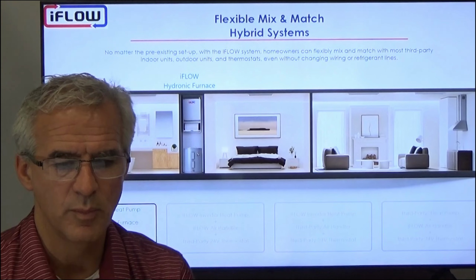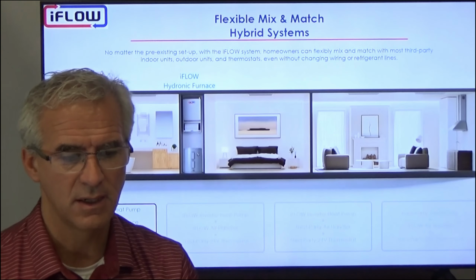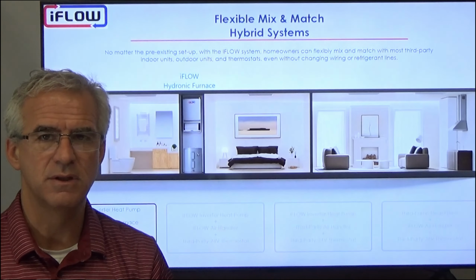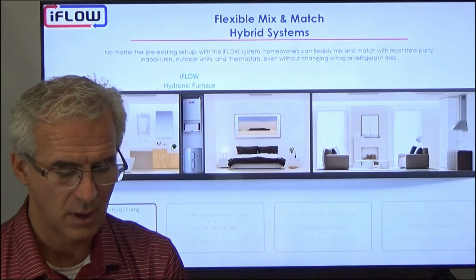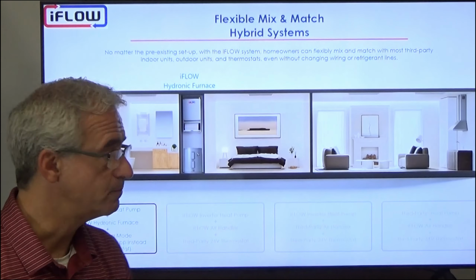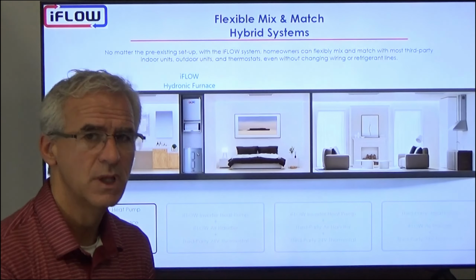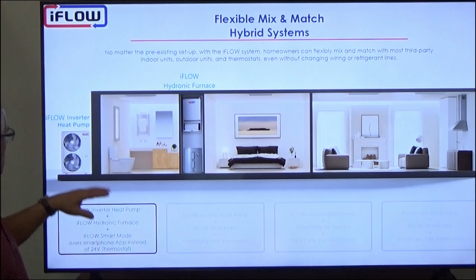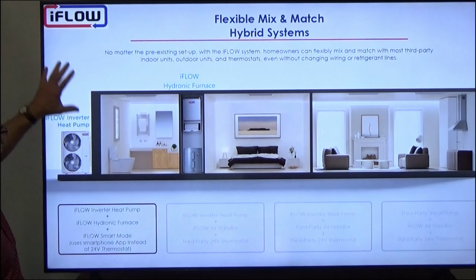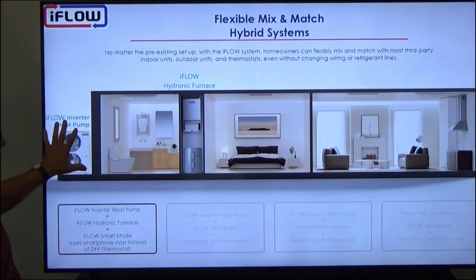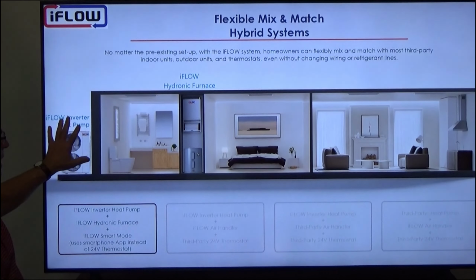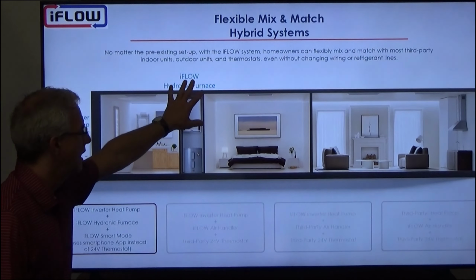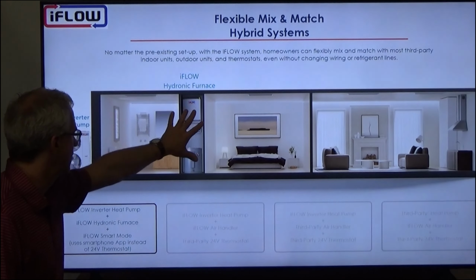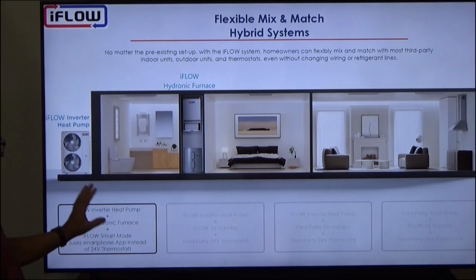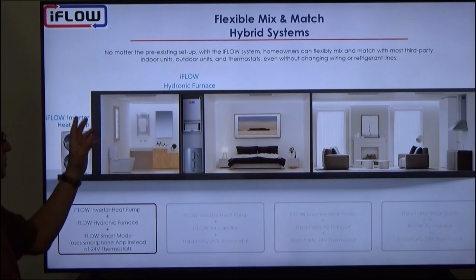In terms of mixing and matching to make hybrid systems, I mentioned that the iFLOW can work in many different situations, so we'll look at a few of them. In this scenario, we're looking at the iFLOW inverter cold climate heat pump on the outside as our condenser unit, and then we have the iFLOW hydronic furnace in the home with the evaporator, and we're using our smart mode to control it.